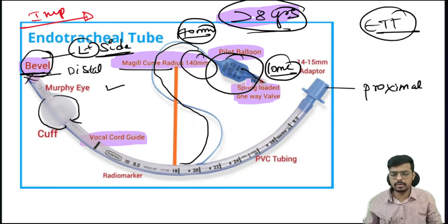Okay, and this particular part is called the pilot balloon. So we will use this pilot balloon to tell whether the cuff is inflated or deflated. Okay, it has a single way loaded spring valve, which means we can insert the air inside, right? And the air will not come back automatically because it has the single way loaded spring valve. If you want to remove the air, you again need to insert the syringe and aspirate the air.